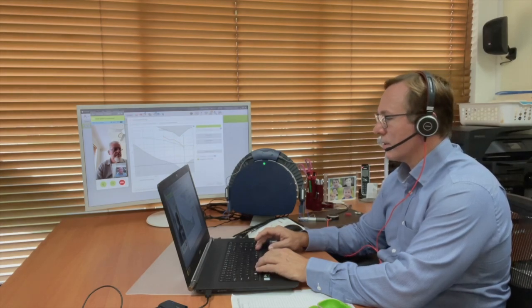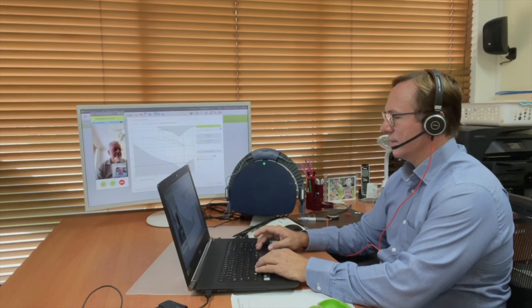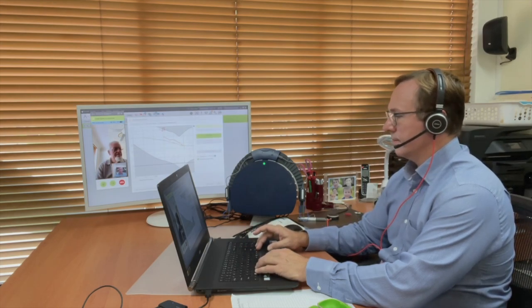During this appointment, we're going to retest Frank's hearing using in-situ audiometry. This is where the hearing aids themselves produce the test tones, and we obtain his hearing thresholds from those test tones produced by the hearing aids. It forms a type of graph we call a Senso-gram or In-Situ-gram. This can then be used to directly program his hearing aids more accurately than using the thresholds obtained under headphones in a booth.